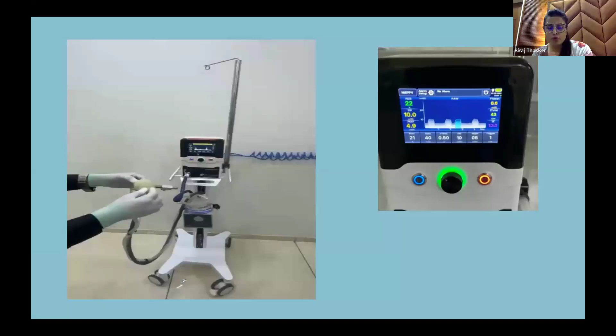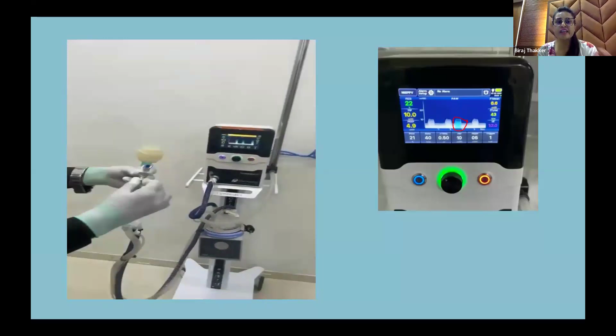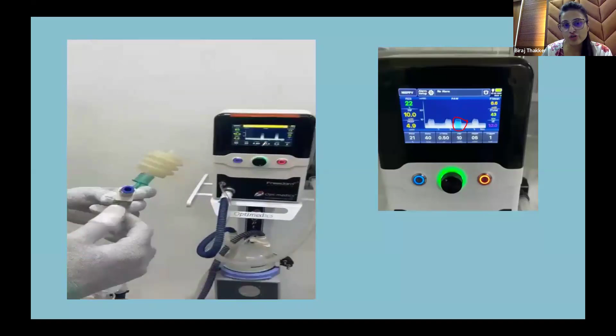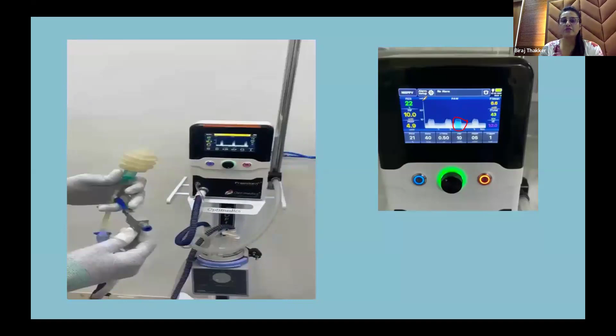And this is the ventilator which I use for giving non-invasive ventilation. I'm not promoting any brand. Here we can see that the white one is the non-triggered breath and the blue one is the triggered breath. What I'm trying to show is that even if there is a leak, if your sensing device is good, it won't show auto triggering. Here it is not showing auto triggering even with a leak. Only when there was a breath, at that time there was a blue breath which was sensed and triggered.